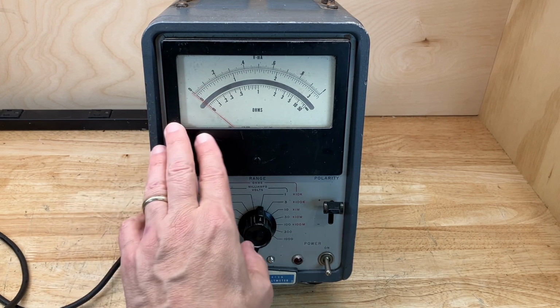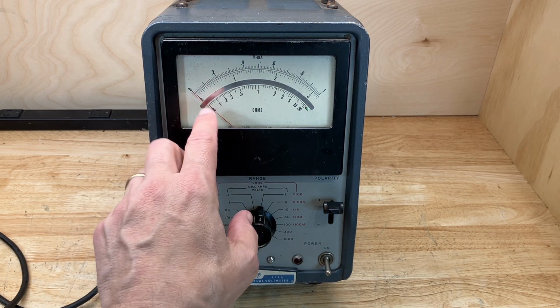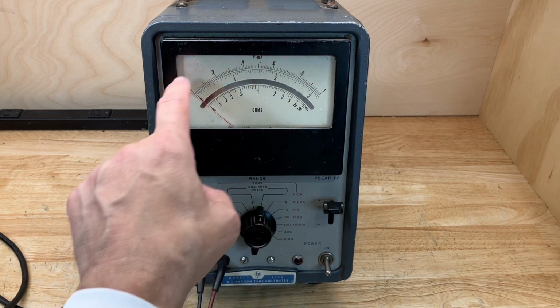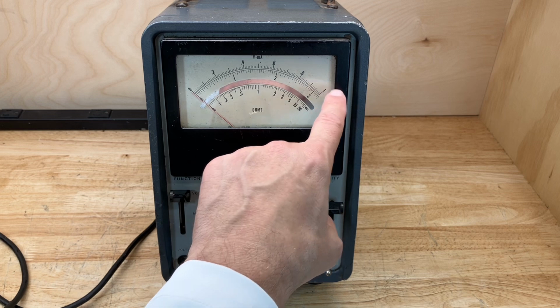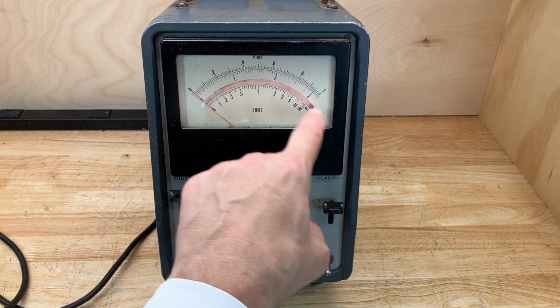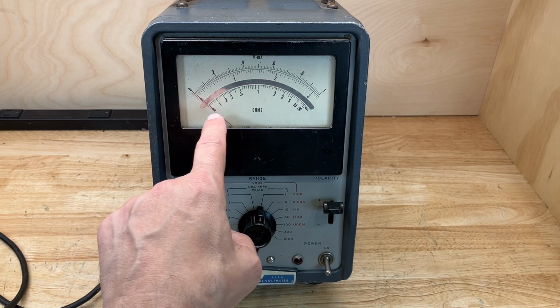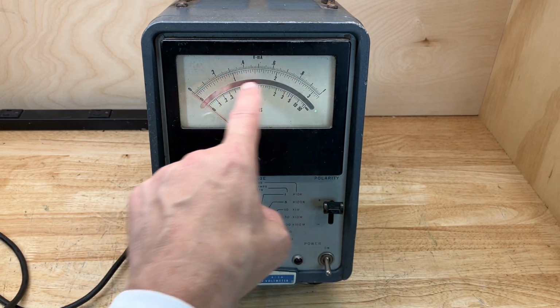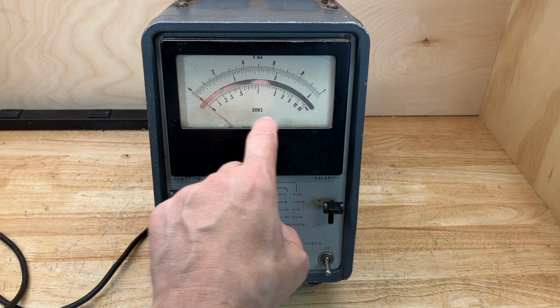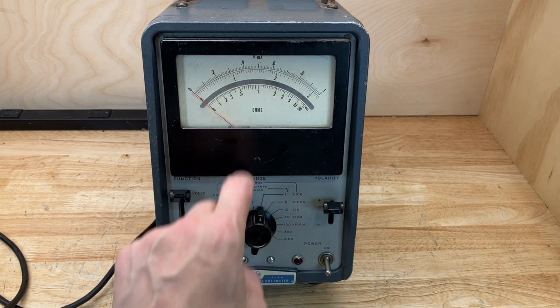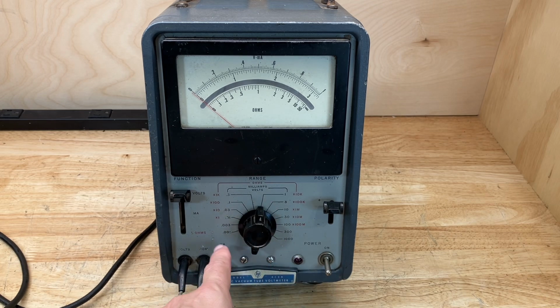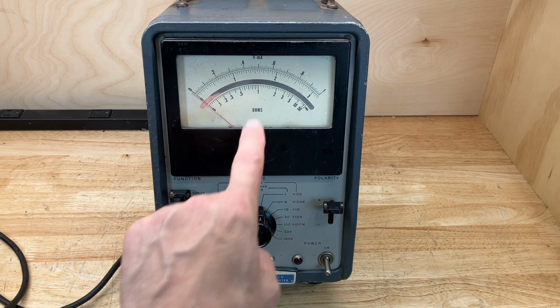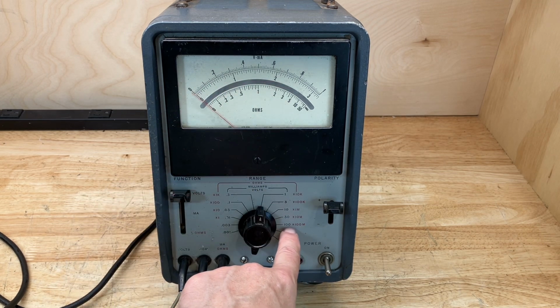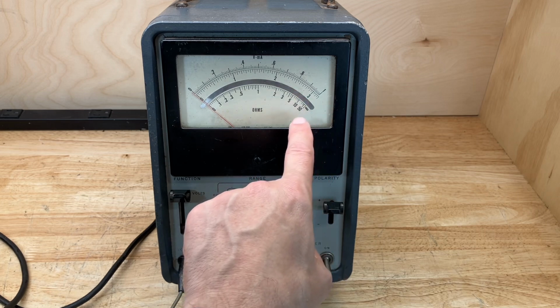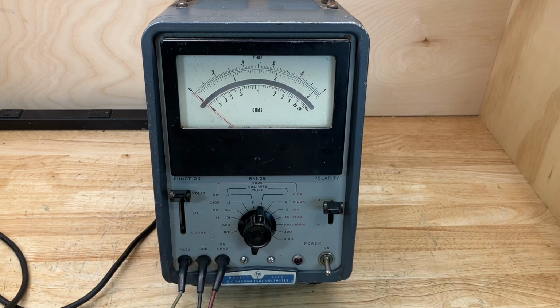The meter movement is a beautiful, large, and easy to read mirrored scale movement with volts and milliamps ranges on the top of the screen and ohms at the bottom. The ohms ranges are logarithmic. Looks like 4 decades of logarithmic displays with a 1 in the center scale. So the center scale on the ohms is equal to the range. So it can measure 1 ohm center scale up to 100 megohms center scale, which means it can really measure greater than 5 gigohms of resistance with this ohm meter.